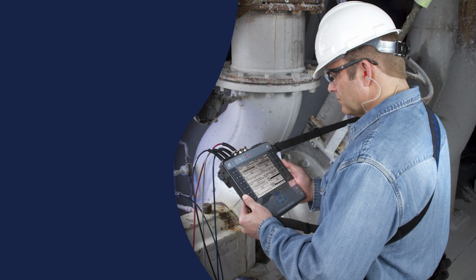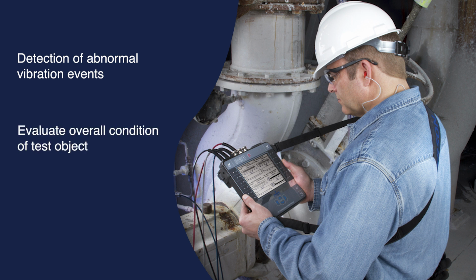Okay, James. So vibration analysis, if I can give you an example, is basically when we take a motor, we would have our sensor and we stick it on the non-drive end. Then once we stick that sensor on the non-drive end, we'd basically be taking vibration of that particular motor. And then we go back to the office and analyze that particular data set. Once we have analyzed it, we're going to give you a frequency spectrum or time waveform, and give you the different failure modes that we detect.